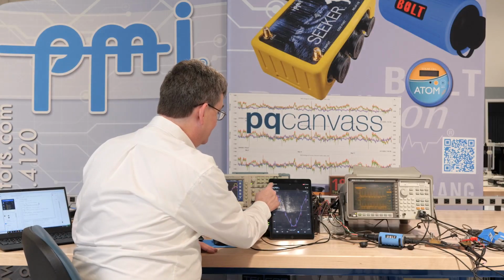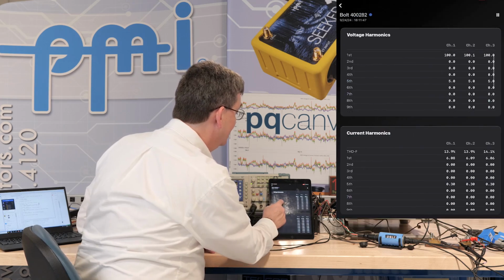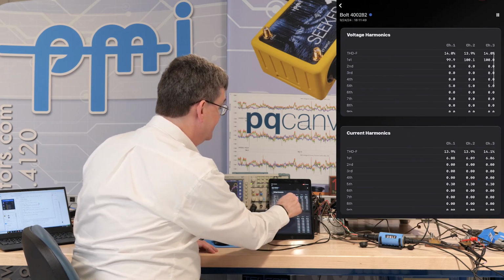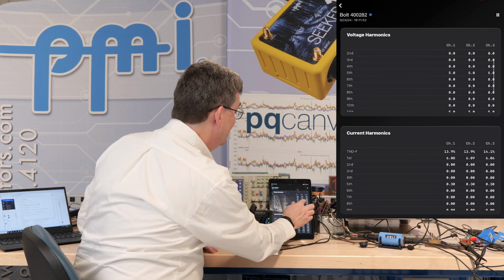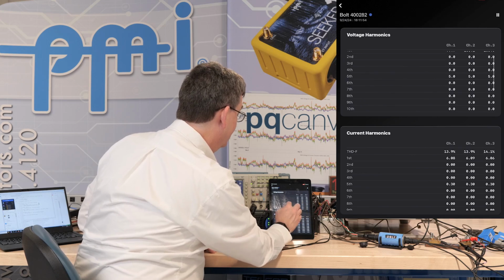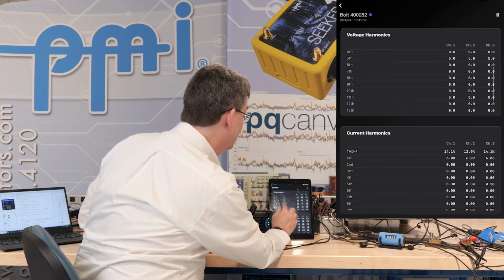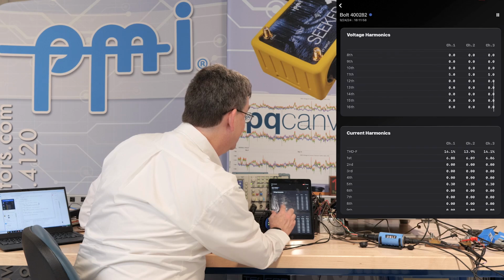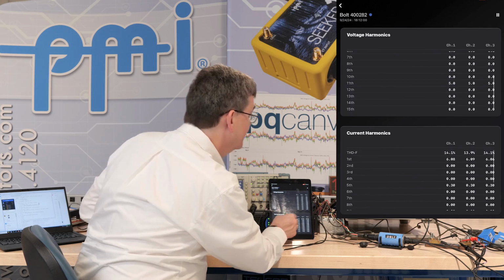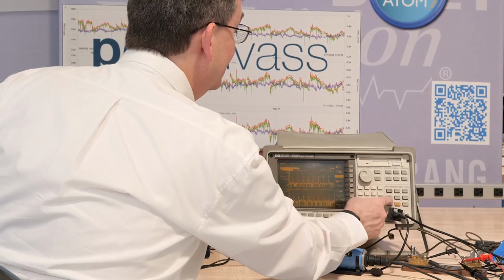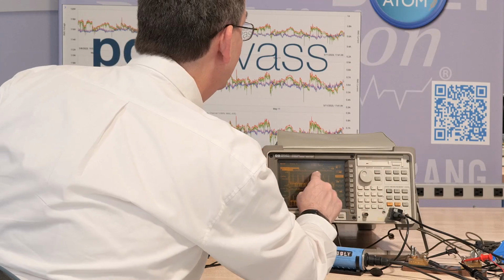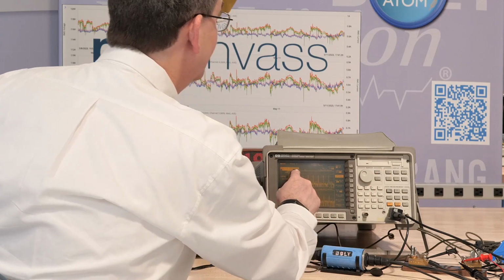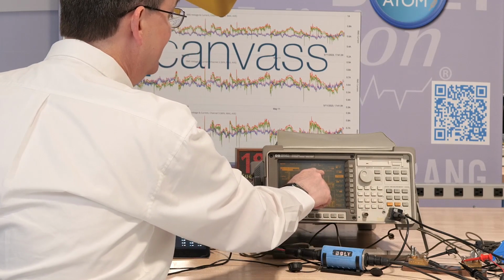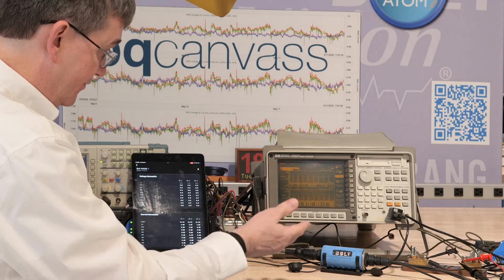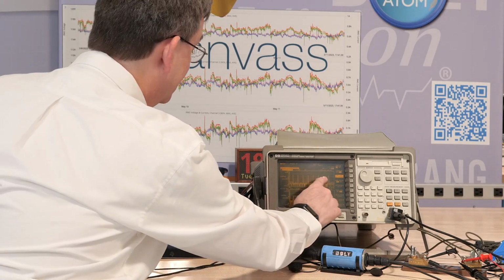Let's check the harmonic levels on the bolt. On the harmonic meter display, we can see 100 volts on the first harmonic, 5 volts for the 5th harmonic, and then the next one we have the 11th harmonic, and so forth up the spectrum, all 5 volts and proportional here for current. Let's corroborate that with the spectrum analyzer. We have the marker at 300 Hertz, the 5th harmonic, and we're reading 250 millivolts, which times 20 is 5 volts. And you can see these are all the same level.